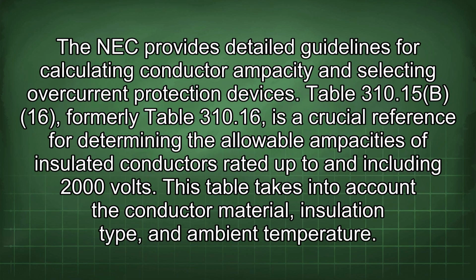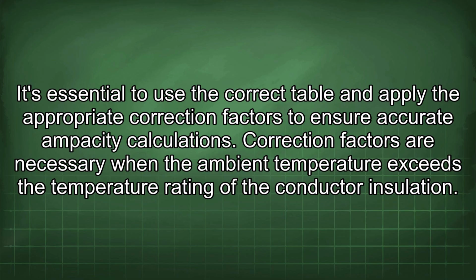The NEC provides detailed guidelines for calculating conductor ampacity and selecting overcurrent protection devices. Table 310.15(B)(16), formerly Table 310.16, is a crucial reference for determining the allowable ampacities of insulated conductors rated up to and including 2000 volts. This table takes into account the conductor material, insulation type, and ambient temperature. It's essential to use the correct table and apply the appropriate correction factors to ensure accurate ampacity calculations.